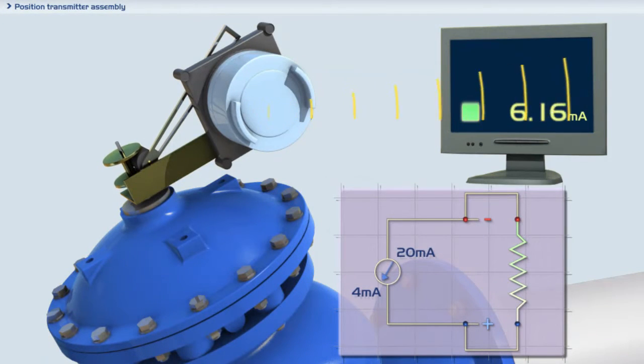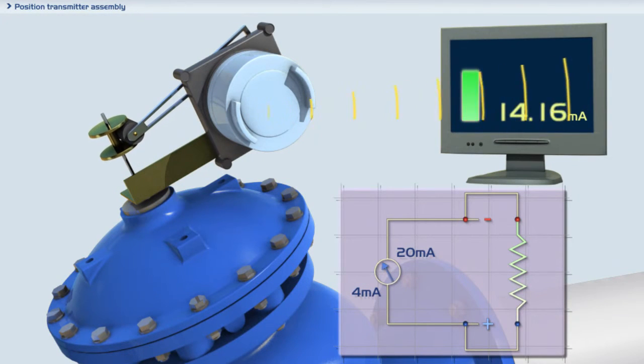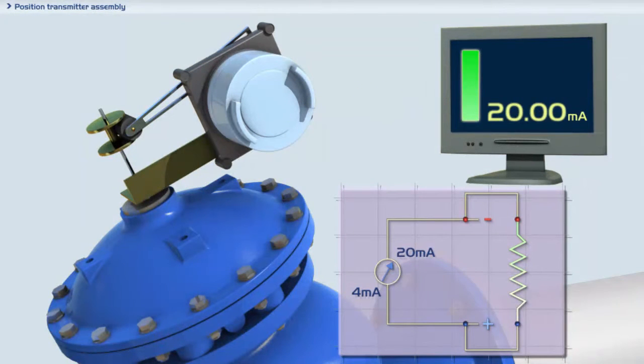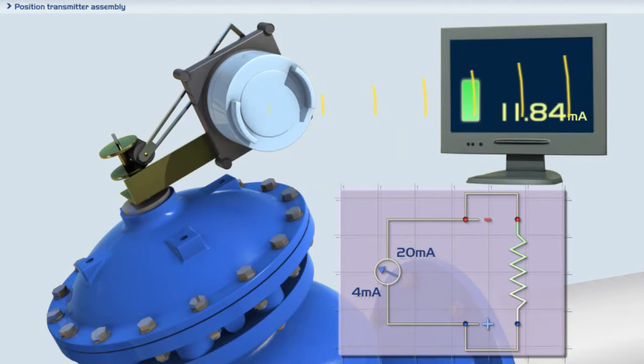The valve position transmitter assembly converts the exact position of the Bermad 700 series valve to a 4 to 20 milliampere current output, transmitting it to a control system, thus allowing for complex smart valve control and regulation.